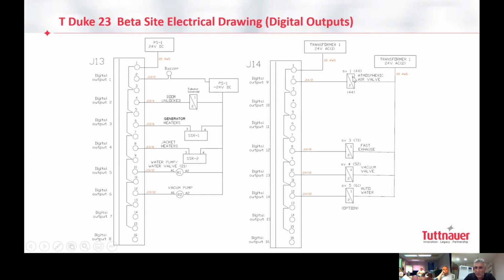You see why we split between the two, right? These are outputs which are operated by 24 volt DC. So the DC is here, in standby for all the outputs, and each one of them gets activated. For example, from 11 it comes to 10, or from this to this, 1 to 2, 3 to 4, 5 to 6.